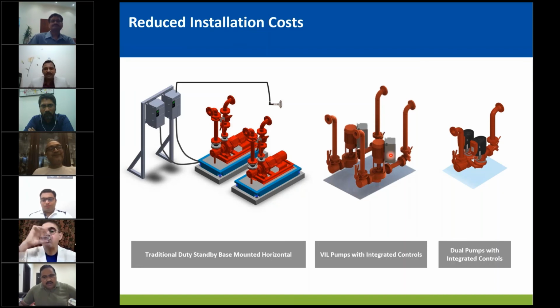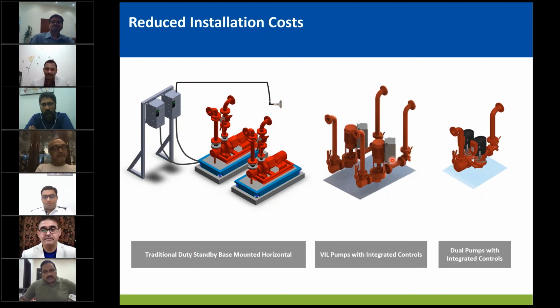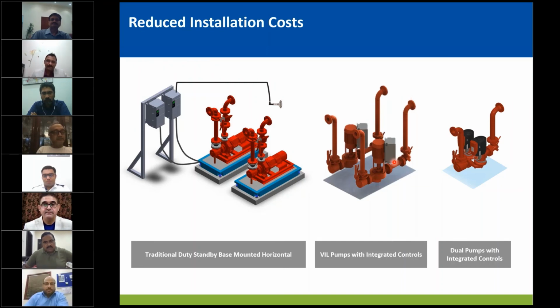Amperage or kilowatt based staging is better in two ways. One, it is the last sensor to fail in the industry, whether you take chillers, pumps, cooling tower fans, or any equipment. If the amperage sensor fails, the equipment is down. That is very specific to a variable speed drive. If the drive fails, the total system is going to be down. So that's the last sensor to fail, number one. Second, it doesn't need calibration over time. Amperage sensors are more reliable and don't drift over time.